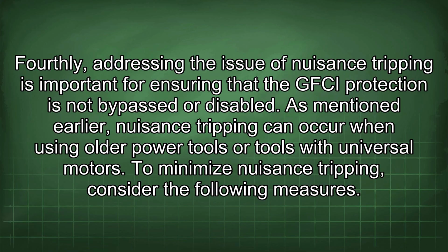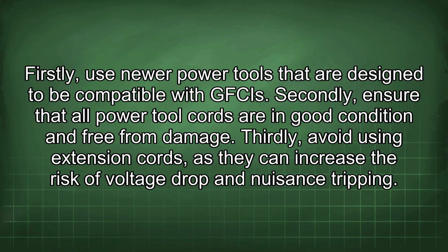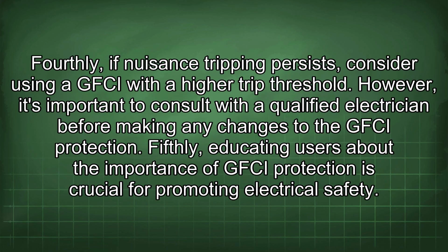As mentioned earlier, nuisance tripping can occur when using older power tools or tools with universal motors. To minimize nuisance tripping, consider the following measures. Firstly, use newer power tools that are designed to be compatible with GFCIs. Secondly, ensure that all power tool cords are in good condition and free from damage. Thirdly, avoid using extension cords, as they can increase the risk of voltage drop and nuisance tripping. Fourthly, if nuisance tripping persists, consider using a GFCI with a higher trip threshold. However, it's important to consult with a qualified electrician before making any changes to the GFCI protection.